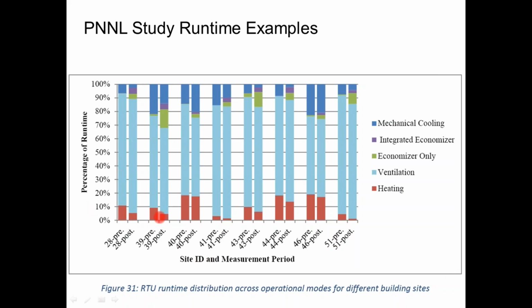The little red bars down at the bottom are how many hours they ran heating in those particular units. The blue bars at the top are how many hours they ran cooling. Green was the economizer hours. Purple was integrated economizer, so both compression and economizer. Then baby blue was when they were doing neither heating nor cooling and were just doing ventilation air. So the damper was at ventilation position and the fan was running. That is a lot of hours at just ventilation.